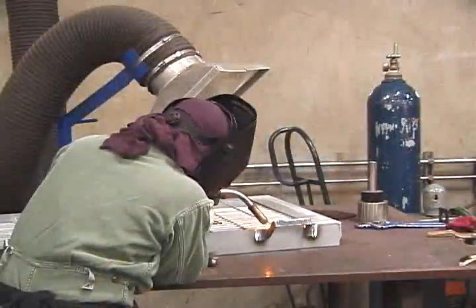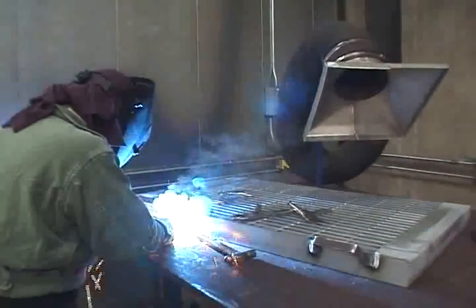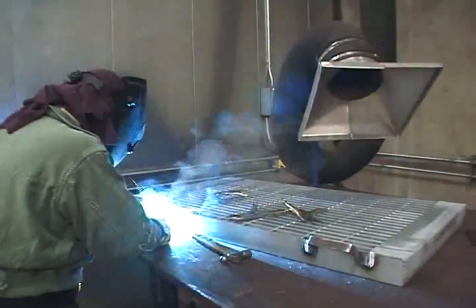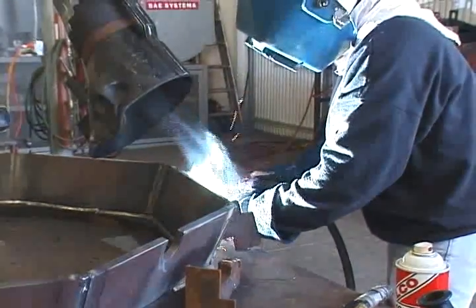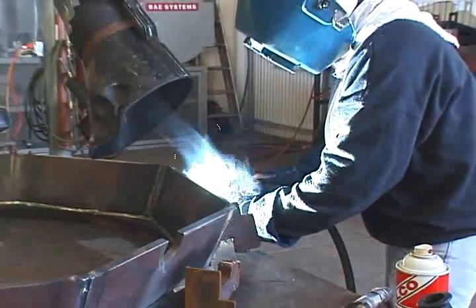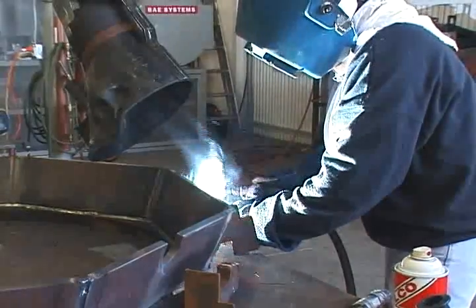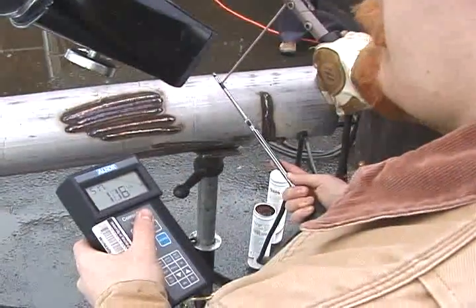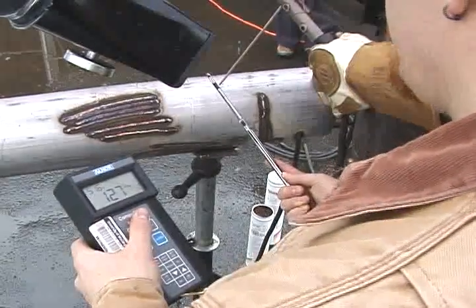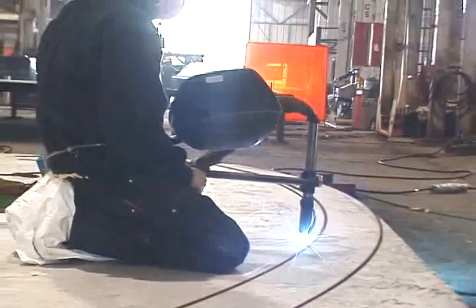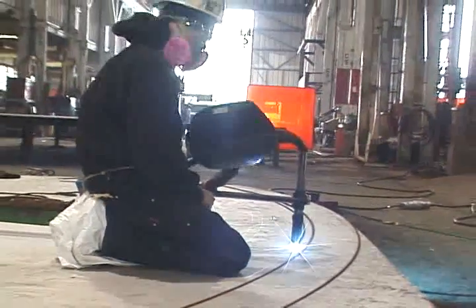Maintaining a capture velocity of 100 feet per minute at the weld also depends on the amount or volume of air in cubic feet per minute being pulled by the fan. Most commercial LEV systems for welding are designed to move the appropriate amount of air needed to use the 1.5 hood diameter rule of thumb. The important thing to remember is to maintain an air velocity at the arc of about 100 feet per minute. It's also important to reduce cross drafts in your welding area so the LEV doesn't have to overcome the competing air currents. This can be done by using welding screens or curtains.